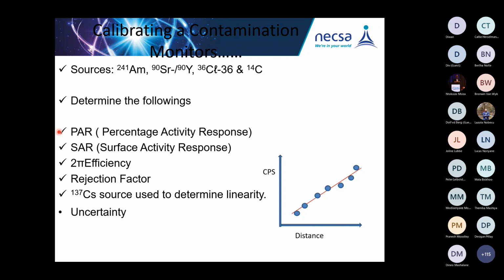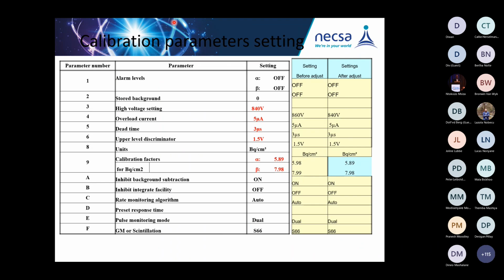In the certificate, we determine the percentage activity response. You will see the surface activity response, 2 pi, rejection factor, like I've said, cesium. This is the content in the certificate. These are the settings before, when the instrument comes. It is quite embarrassing, and quite disturbing, to see an instrument come with 20 volts here, meaning that you can't measure anything if it is set like that. And this is the setting after. The setting after, these are the settings that you use every time you take your instrument to the field.